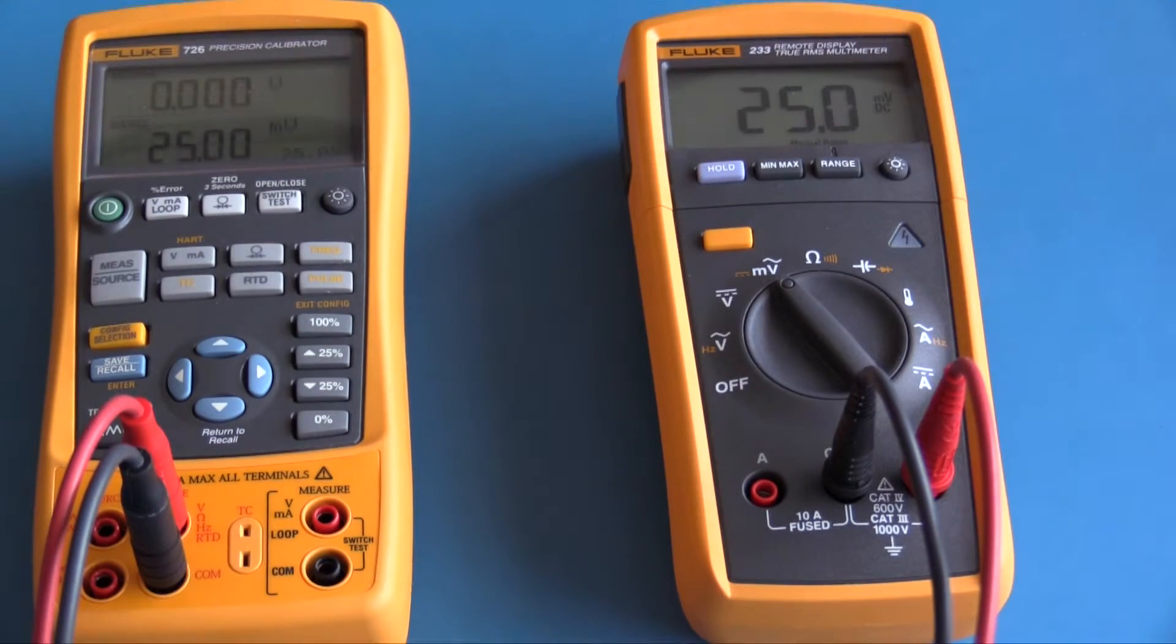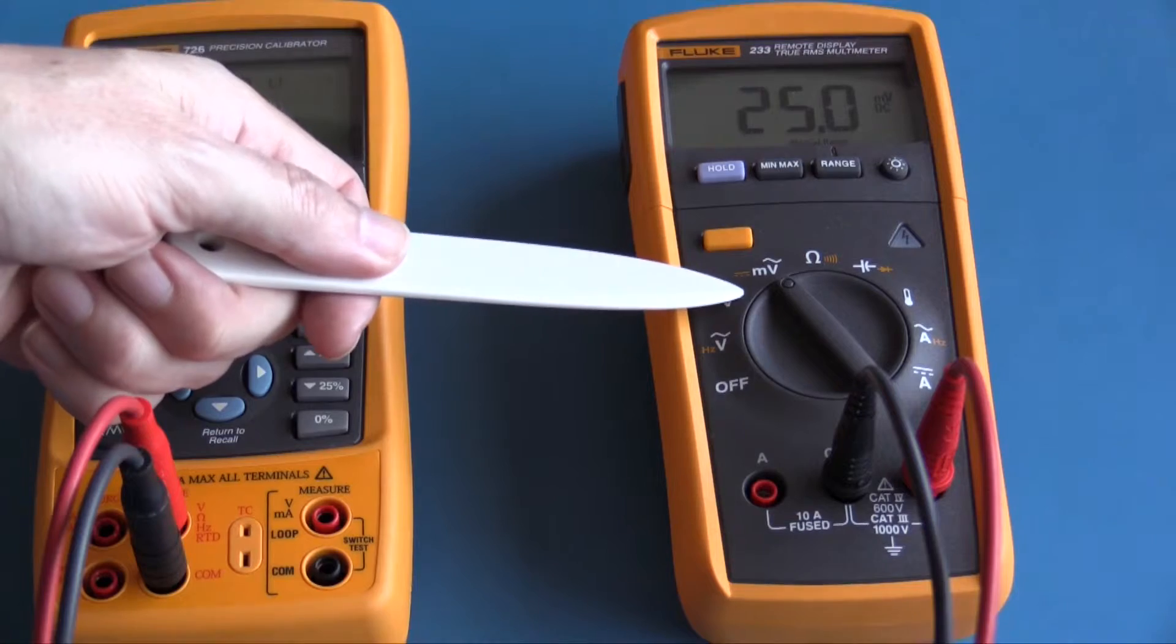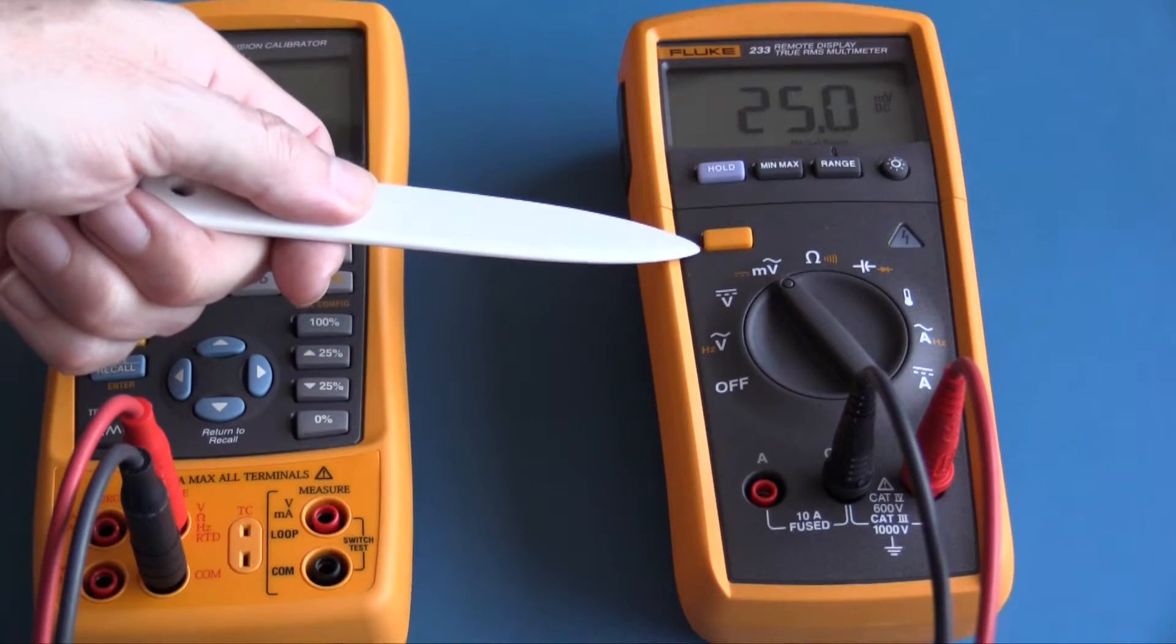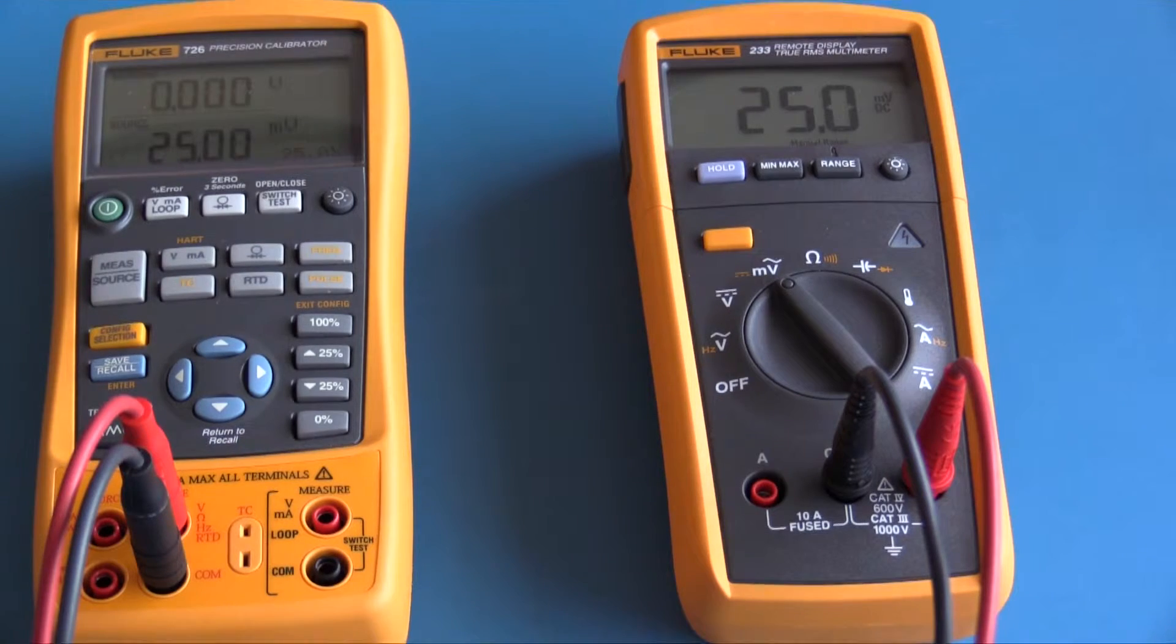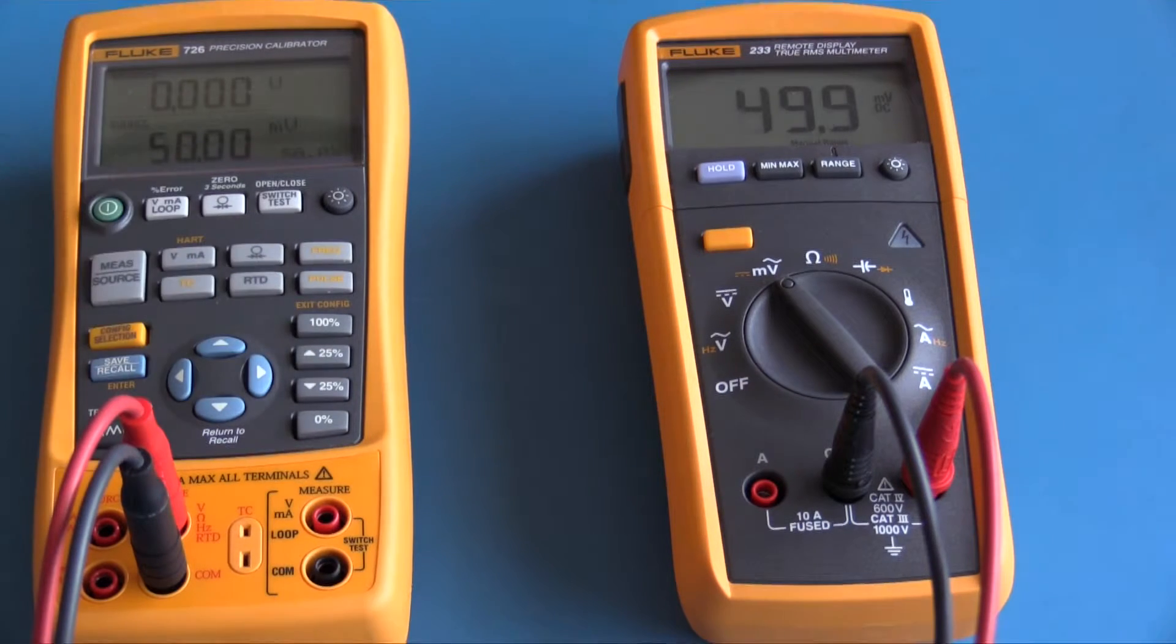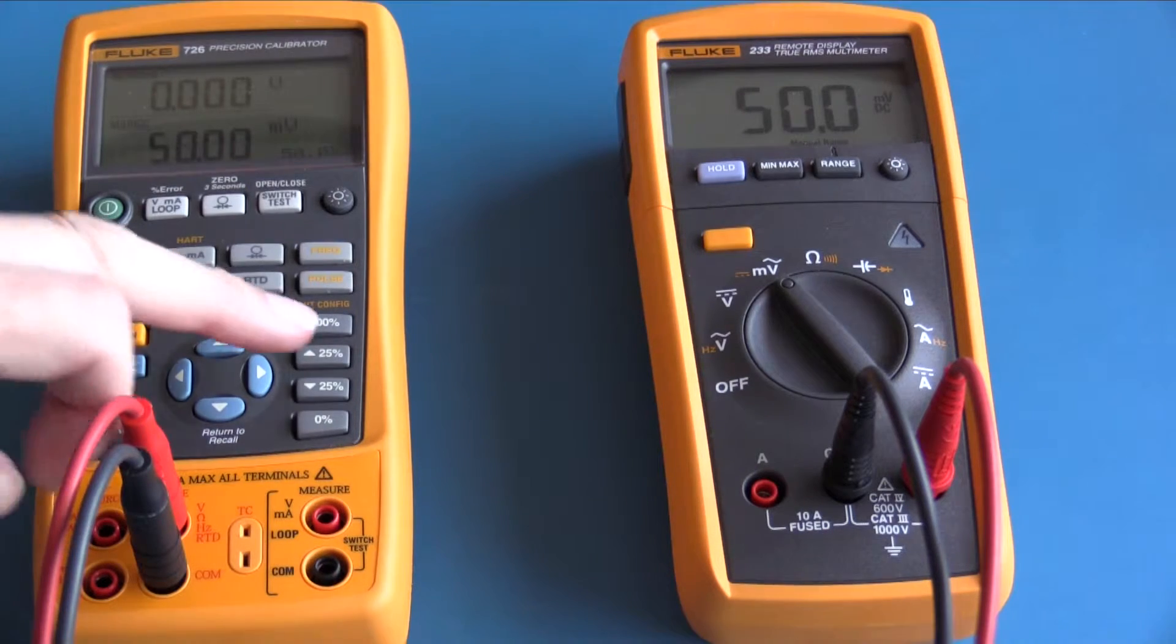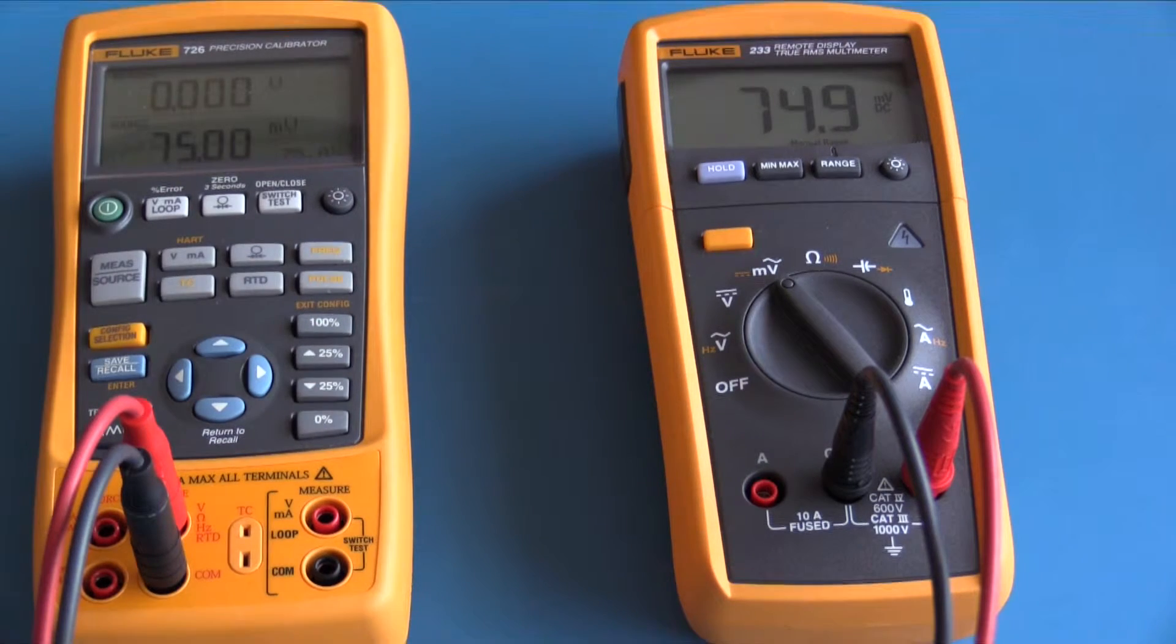I now have the Fluke 233 set to its millivolt range and I have selected the secondary function DC millivolts. The Fluke 726 is set to source an accurate 25 millivolts. The Fluke 233 is showing exactly 25 millivolts. This is 50 millivolts and again the Fluke 233 is showing 50 millivolts. 75 millivolts, very close, and this is 100 millivolts. Although a very basic electrical meter, it's quite accurate.